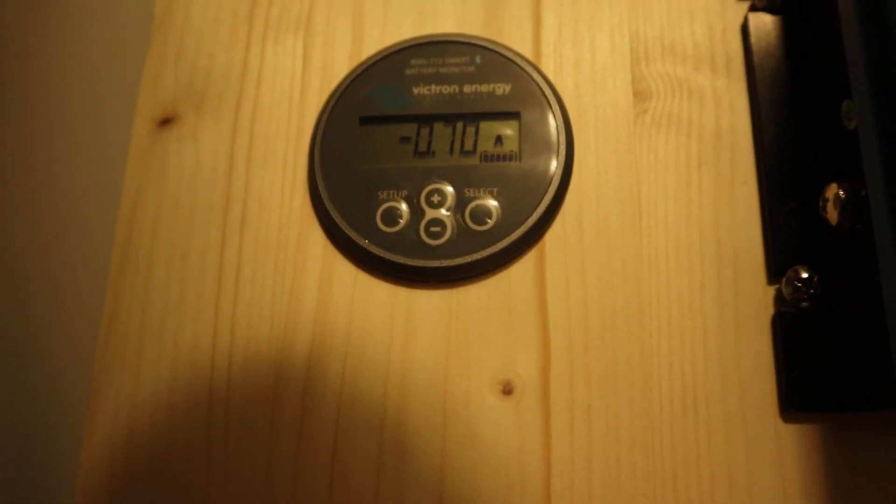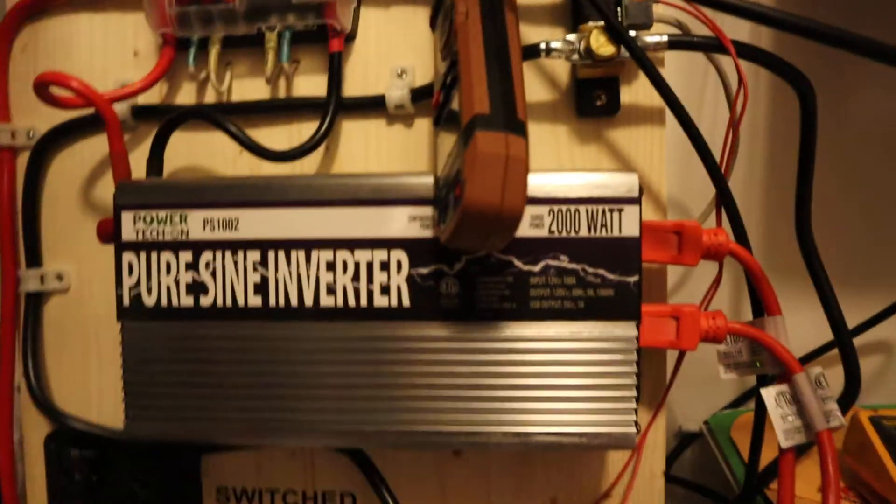As you can see I've got about 0.63, it's best to try to get it centered here as well as you can. I'm getting 0.71 and up here I've got about 0.70 to 0.71, so my system's calibrated now.